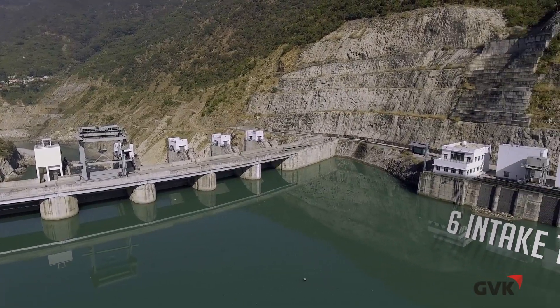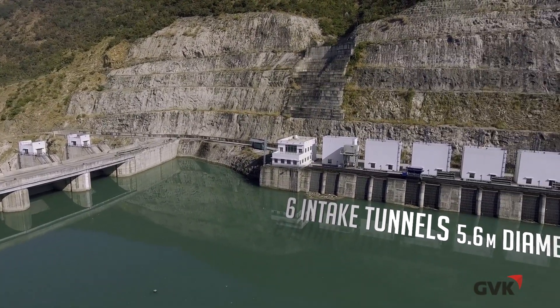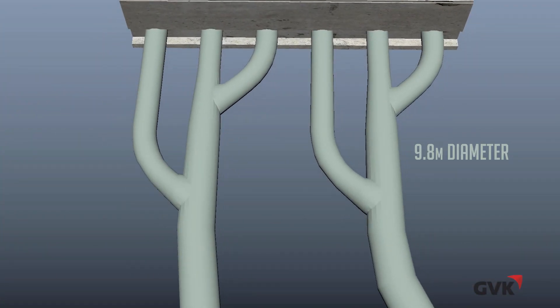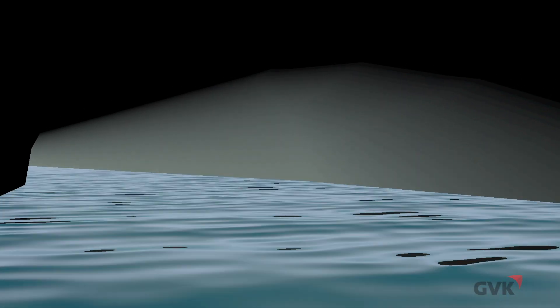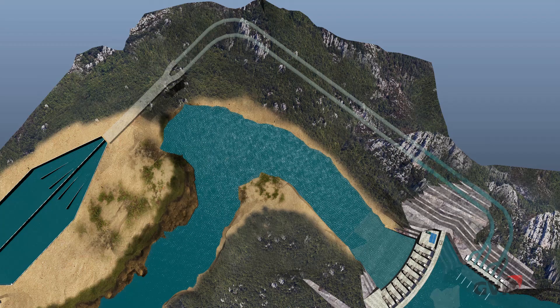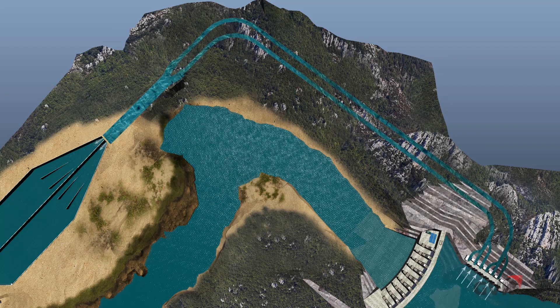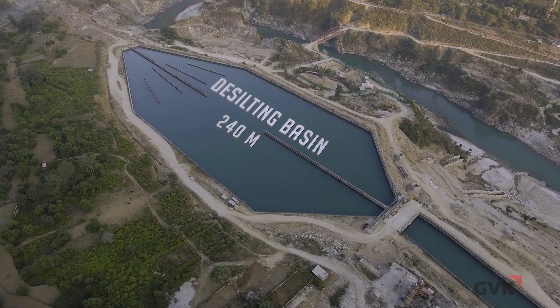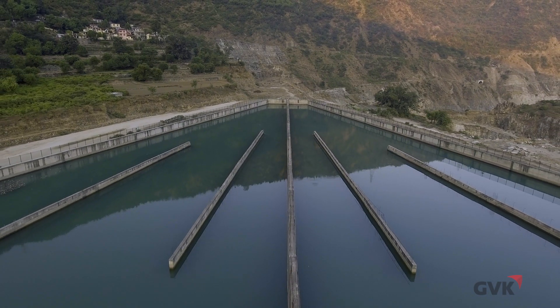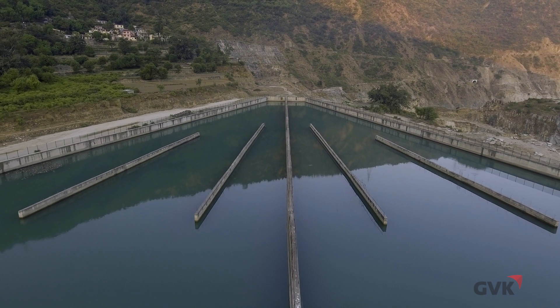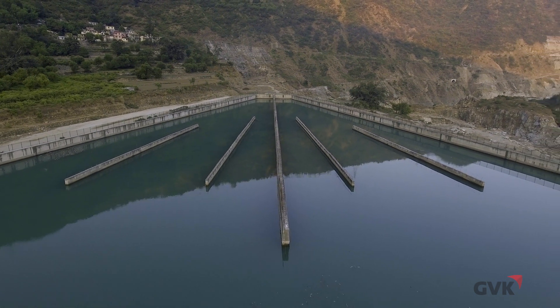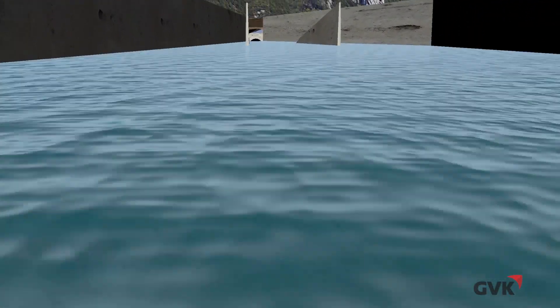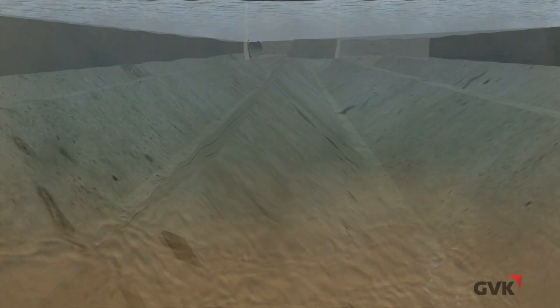Six intake tunnels, each 5.6 meters in diameter, have been built upstream to divert the water into two main head race tunnels of 9.8 meters diameter each. Through these head race tunnels, the water travels more than a kilometer to reach the desilting basin. This 240-meter-long desilting basin is designed so that the turbulent flow of water coming from the head race tunnels converts into laminar flow. Silt particles of sizes larger than 0.2 mm are trapped.